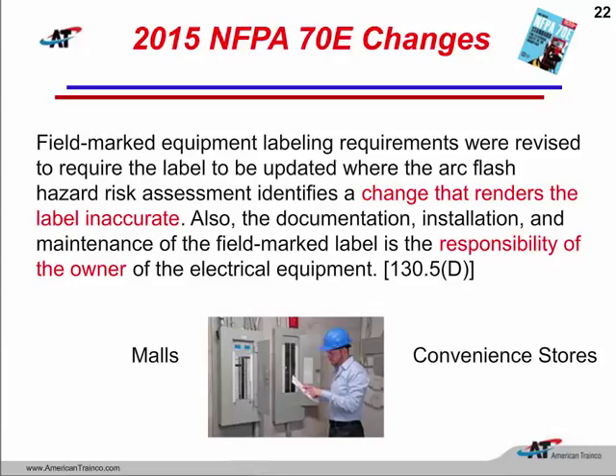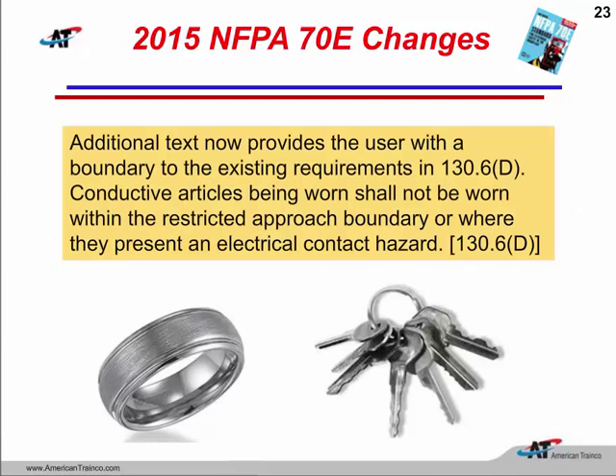A lot of times in the manufacturing world, we work in a building and the owner of the company actually owns the equipment, so they would be responsible for that. But there are going to be times when the owner of the equipment is not the person that's inside that particular premise. So the owner is going to have to make sure that that label is installed and it's perfect in one method or the other. They also gave us an idea that inside that restricted approach boundary, we cannot wear anything that is conductive. So they added some additional text there. We're going to have to make sure that anything that is conductive comes off our body before we go inside that restricted approach boundary. And that is up in Article 130.6 also, so we want to make sure that that is something that's inside of our electrical safety program going forward.